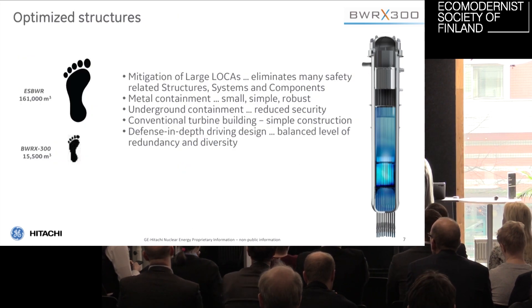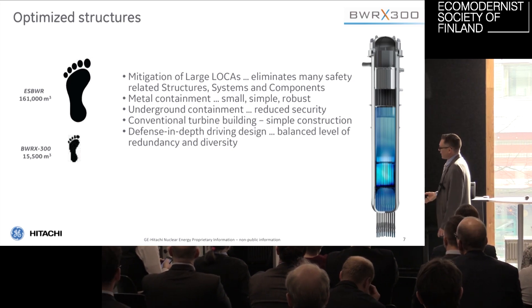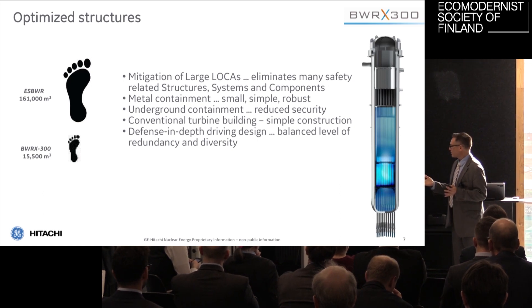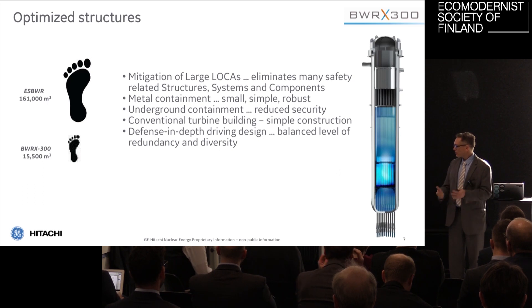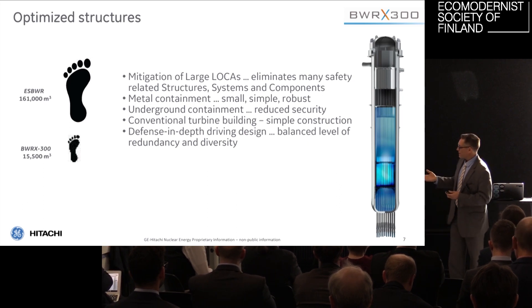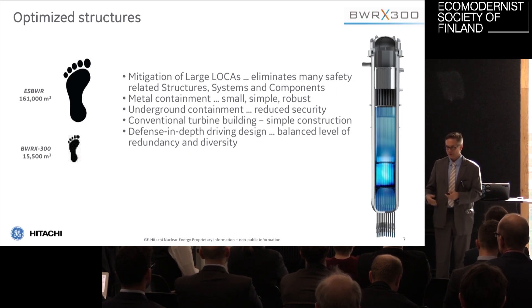By optimizing structures and making this LOCA feature work, and making safety systems either not needed or accomplished by already existing systems, we can use a metal containment — small, simple, robust — with an underground structure. We use a conventional turbine building with very simple construction. We started from the very beginning with defense in depth in the safety case, because it's actually really cost-effective if you start that way. If you start with those principles at the beginning of the design work, it doesn't cost any more, and it's very easily translated back to the US once established for the base plant. Defense in depth drives you to make the right decisions in diversity, separation requirements, redundancy requirements, and design rules for each defense line in terms of safety classification, which can be country-specific, especially on the procurement side.